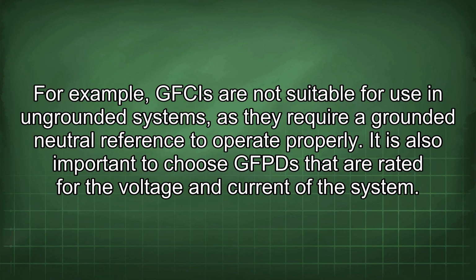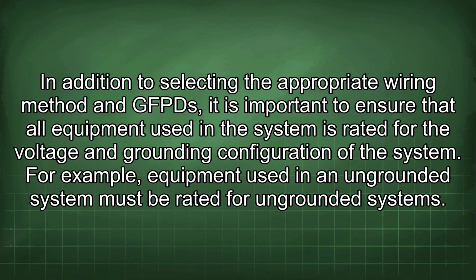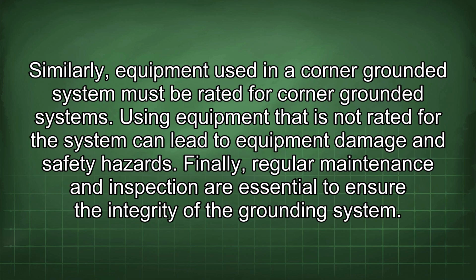It is also important to choose GFPDs that are rated for the voltage and current of the system. In addition to selecting the appropriate wiring method and GFPDs, it is important to ensure that all equipment used in the system is rated for the voltage and grounding configuration of the system. For example, equipment used in an ungrounded system must be rated for ungrounded systems. Similarly, equipment used in a corner-grounded system must be rated for corner-grounded systems. Using equipment that is not rated for the system can lead to equipment damage and safety hazards.